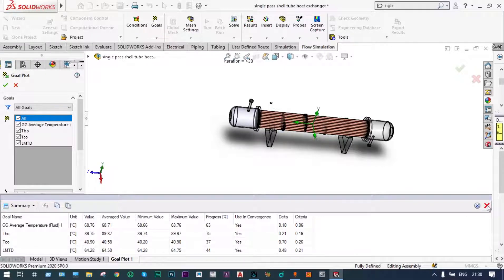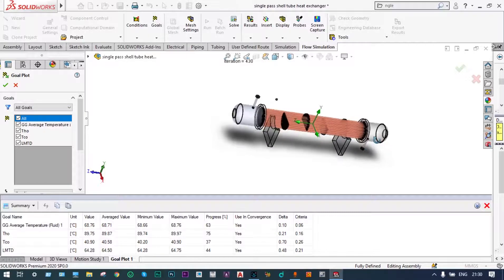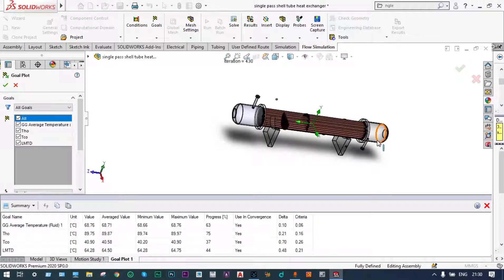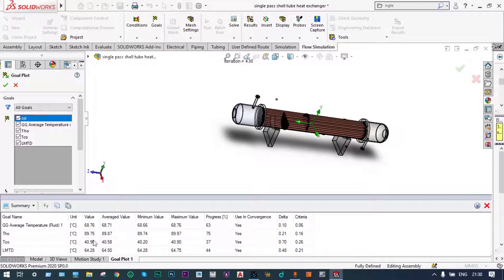In this CFD analysis, the initial temperature of hot water was 100 degree centigrade and at the exit level its temperature came down to 89.75 degree centigrade. Similarly, initial cold water temperature was 20 degree centigrade and finally at the exit level its temperature is 40.9 degree centigrade and LMTD value is 64.28.